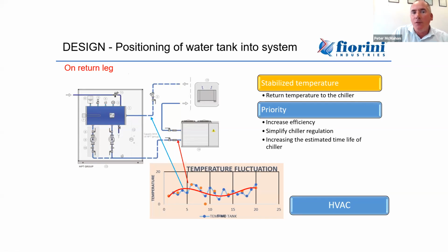The positioning of the buffer tank is very often underestimated. So I've 3 slides here to explain the differences in where you locate your buffer tank. So the first application here, we can see we have your heat pump here. We're pumping our water out. Let's just call this a chiller for argument's sake. So we're pumping our chill water out to your system.